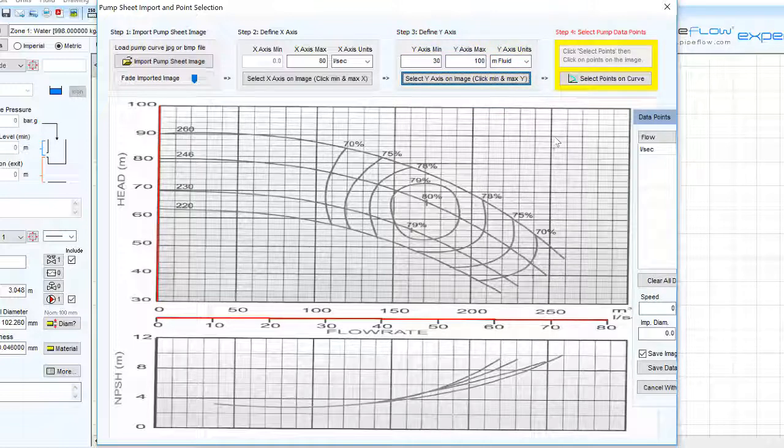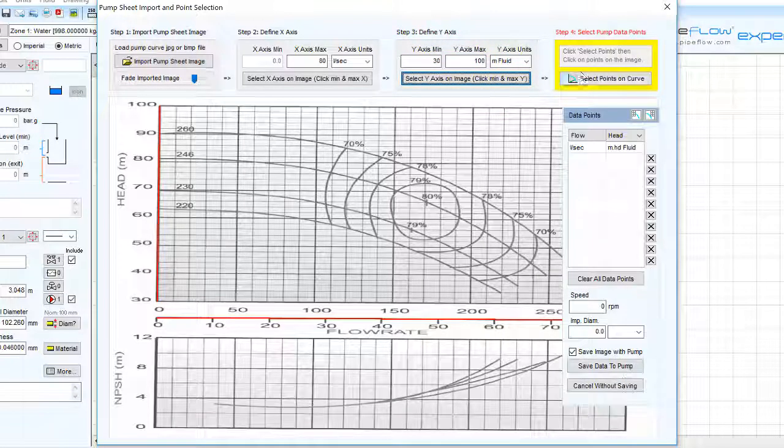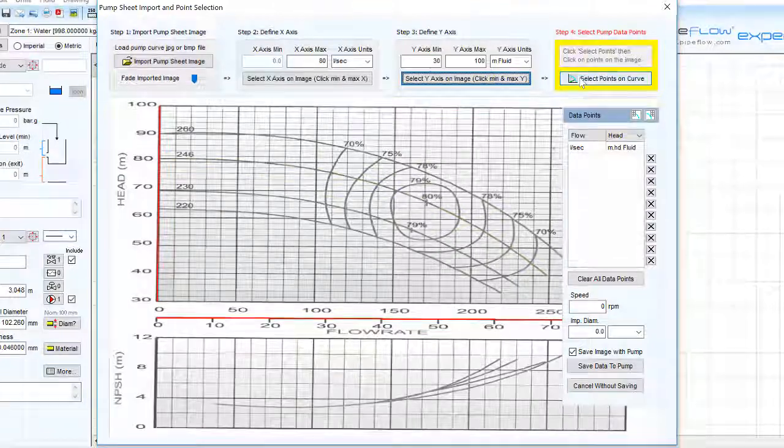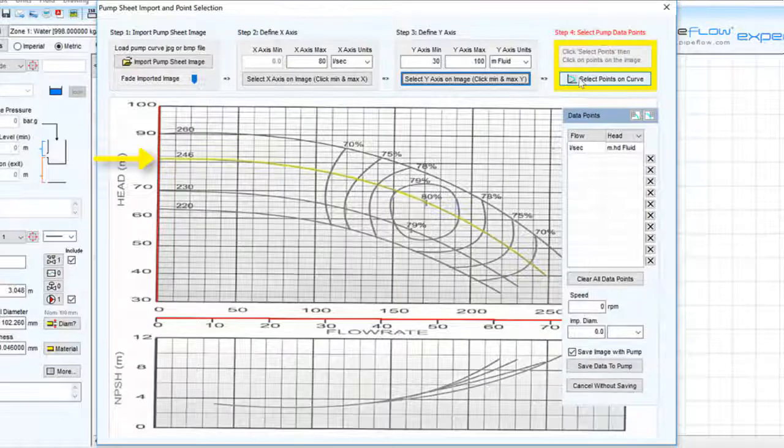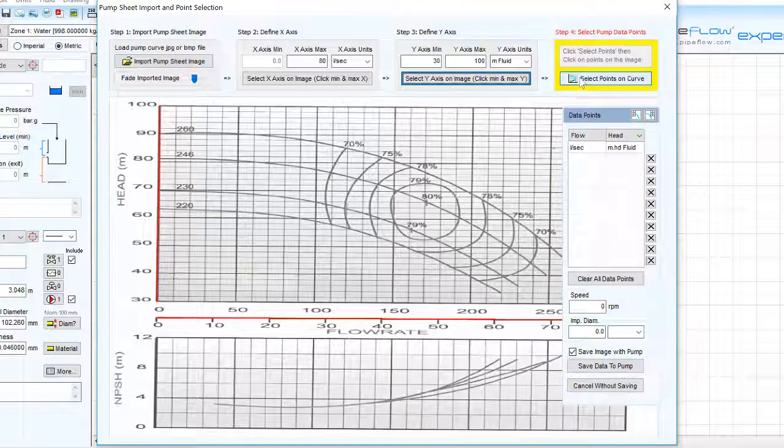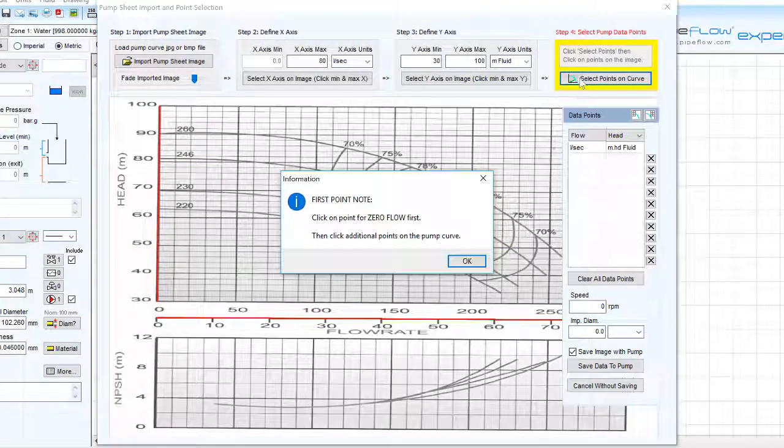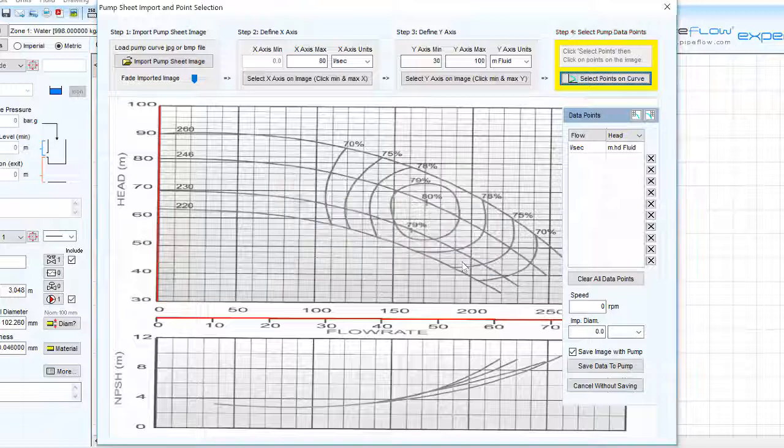Next we select a curve and begin defining points using the select points curve button. It is best to select a curve roughly in the middle of the curves defining the performance for the minimum and maximum impeller diameters. As our first point we must identify the shut off head point at zero flow for our chosen curve.